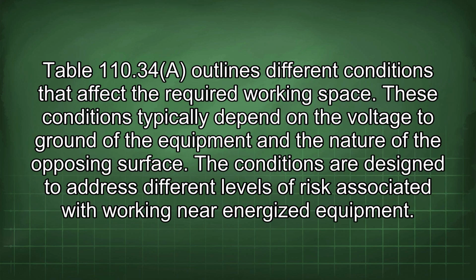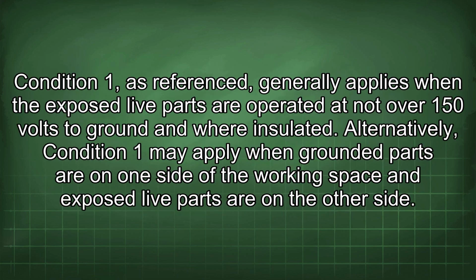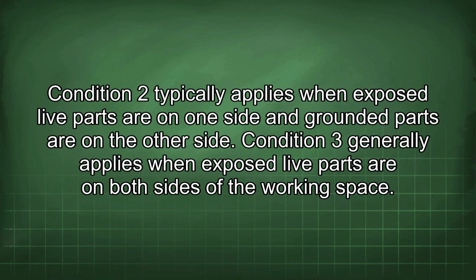Table 110.34 outlines different conditions that affect the required working space. These conditions typically depend on the voltage to ground of the equipment and the nature of the opposing surface. The conditions are designed to address different levels of risk associated with working near energized equipment. Condition 1, as referenced, generally applies when the exposed live parts are operated at not over 150 volts to ground and where insulated. Alternatively, Condition 1 may apply when grounded parts are on one side of the working space and exposed live parts are on the other side. Condition 2 typically applies when exposed live parts are on one side and grounded parts are on the other side. Condition 3 generally applies when exposed live parts are on both sides of the working space.